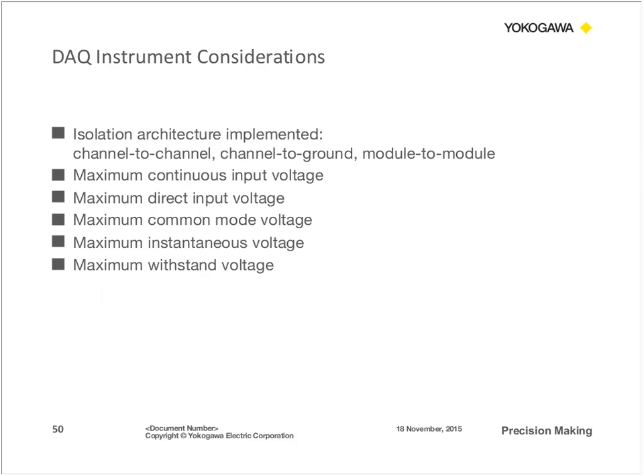So when it comes to choosing the right data acquisition instrument, what you should be careful or consider is, first of all, the isolation architecture. Does it implement these three things: channel-to-channel, channel-to-ground, and module-to-module isolation? And this is going to provide you with the best noise immunity and the most accurate measurements.